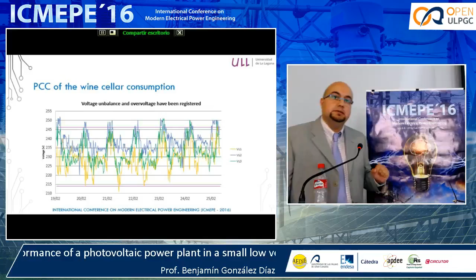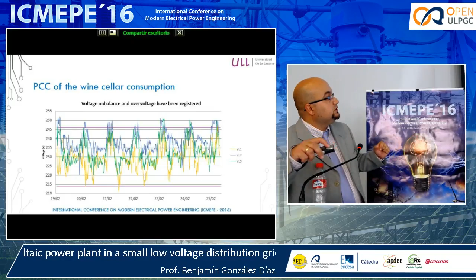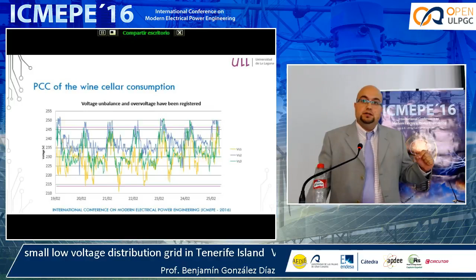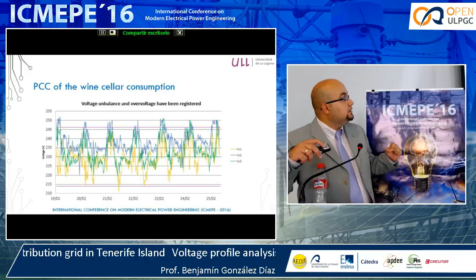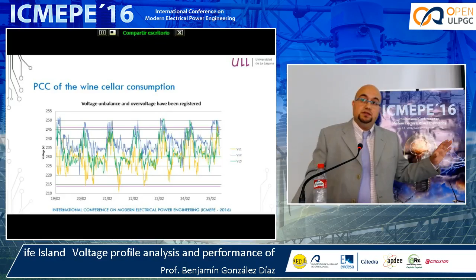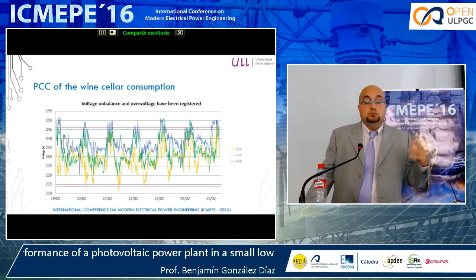We have a problem here. We can see that in line 2, the voltage profile is higher than the upper limit. And in the case of line 1, the voltage is lower for several days. And we are not in the peak position during the season. We are exactly here in these days. So we have a problem: when the PV power plant production and the consumption are higher, the voltage will increase.